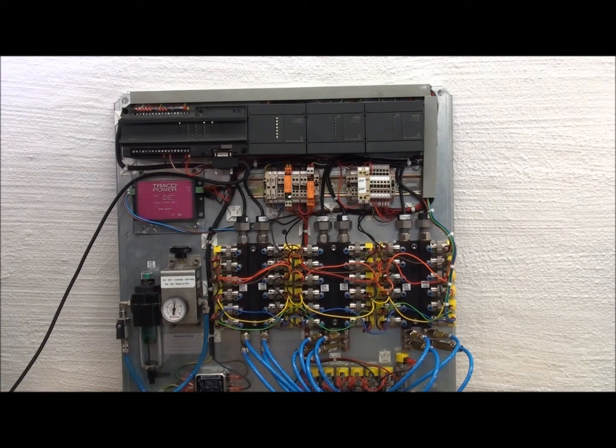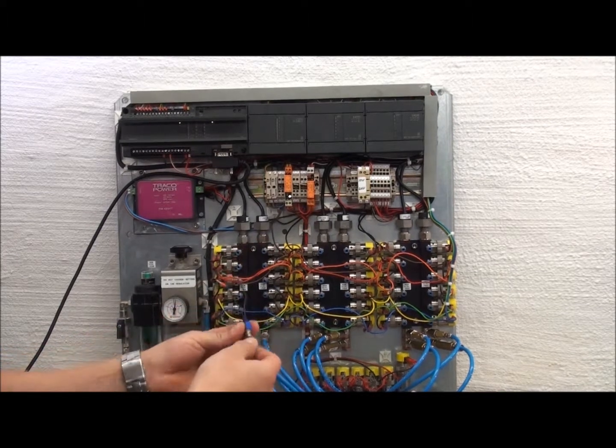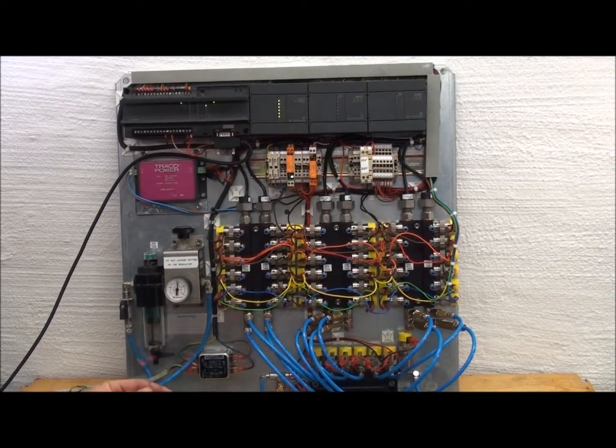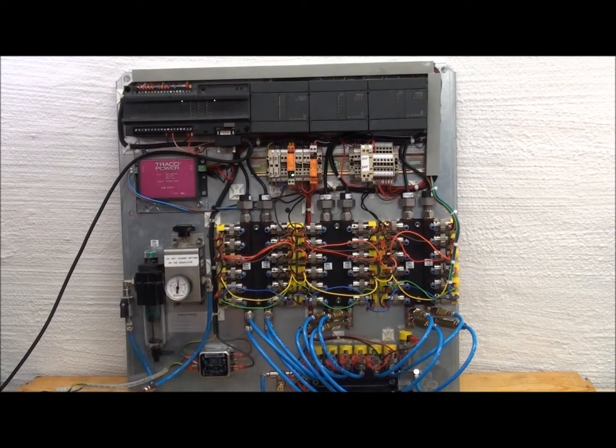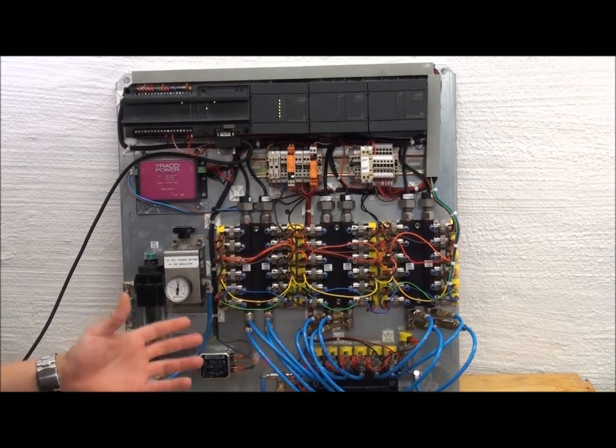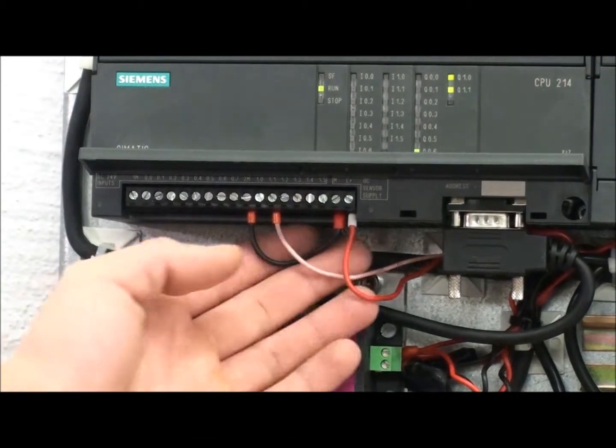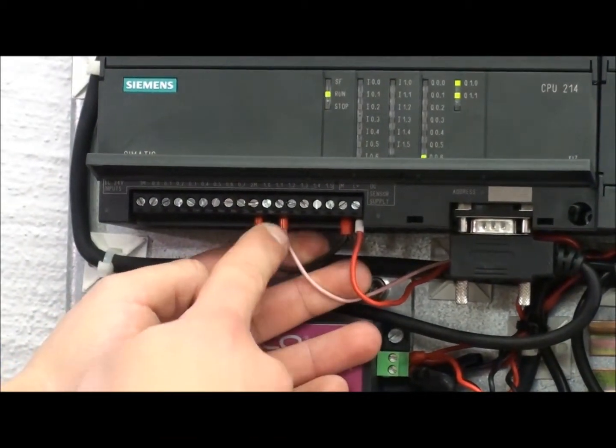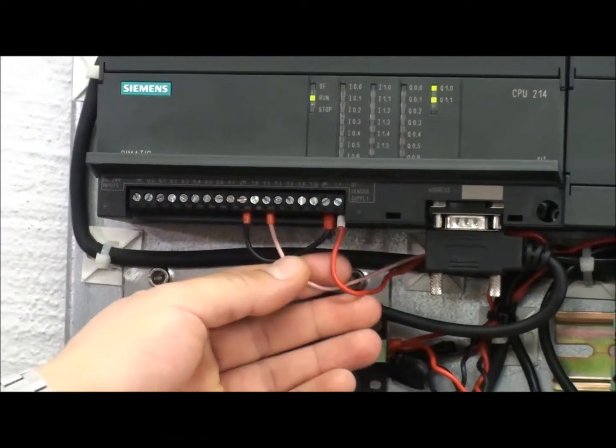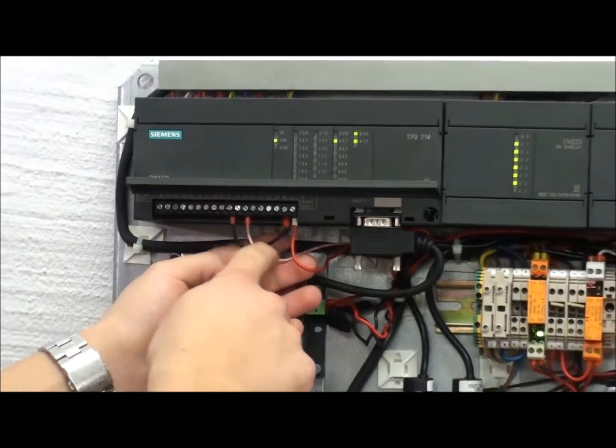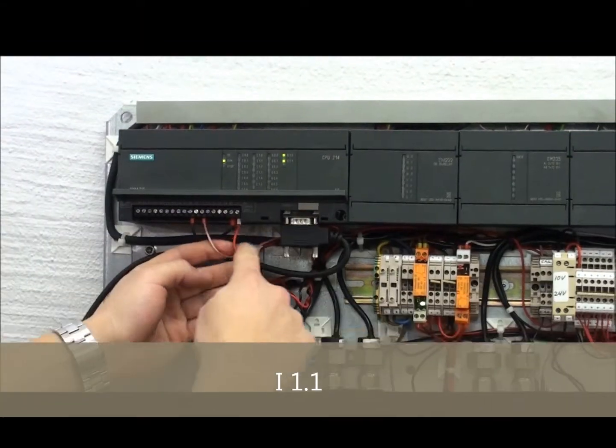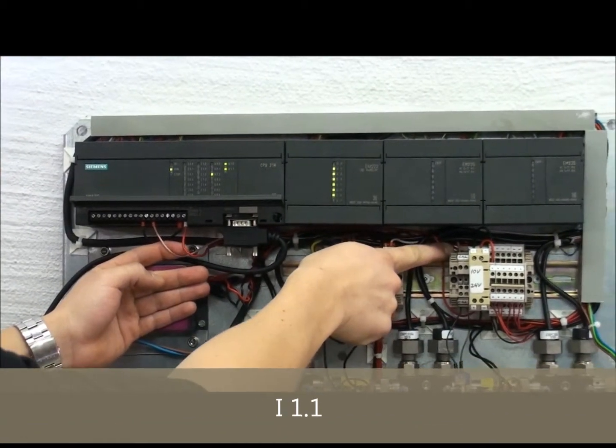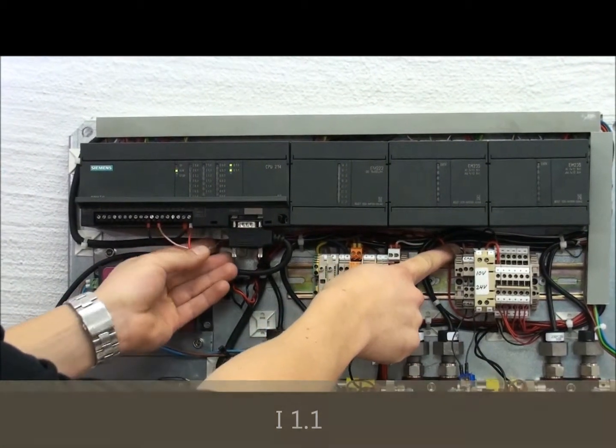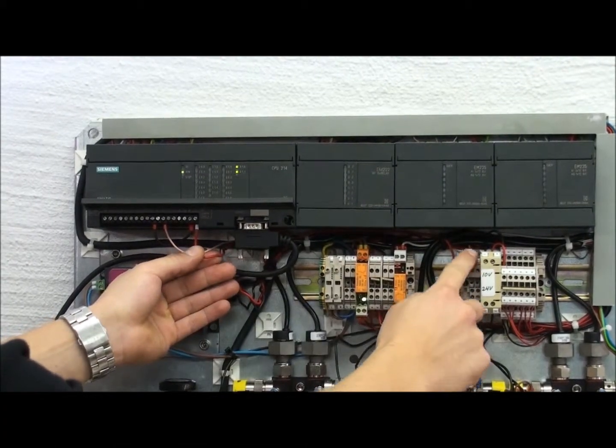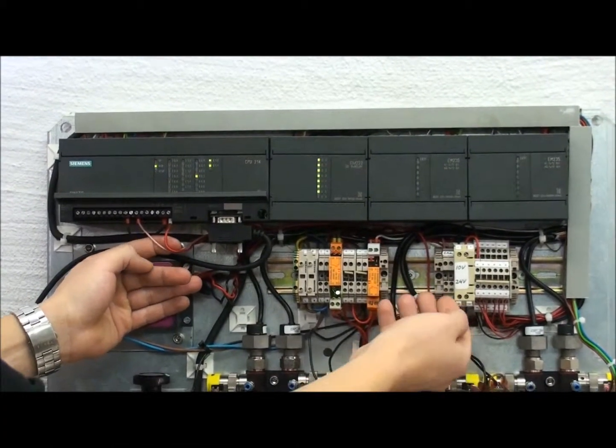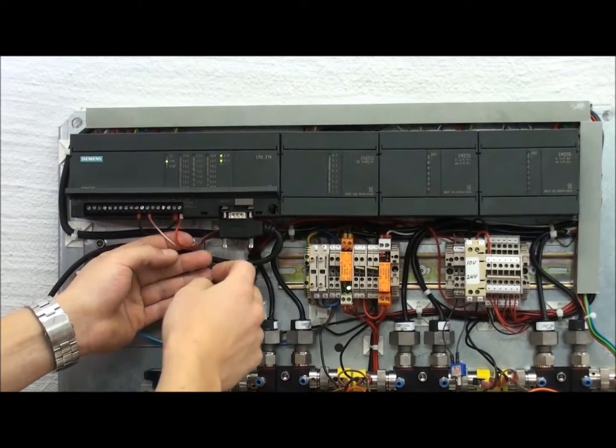So to do that, you need one of these switches, the one we have been using the whole time. And that's pretty much everything, because we already did all the dirty work. So if we follow this cable here, the pink one, it's almost always pink. So the pink one is made for calibration. And this cable comes here, and you see here there is another pink cable, which is the same one. And then you just make a bridge in between that. You just put a jumper in between these two cables. Actually, that's what you do here.